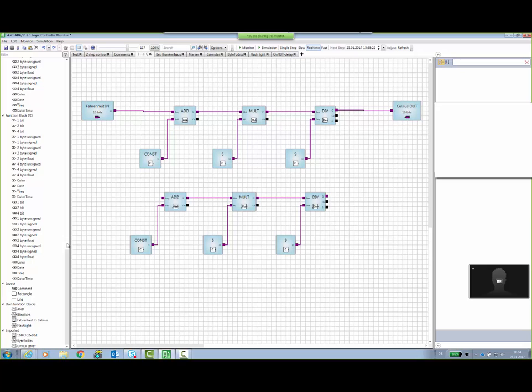To create a function block now, I have to take not the normal KNX inputs and outputs, as we have here, but function block IOs, as you see here on the left as well. So the same data types, but named function block IOs. In this case it's a temperature value, which is a 2-byte float value. So I take the 2-byte float value as a function block input, FB input so-called, and I connect it to this input. And the same I need for the output. I connect it here, that's the output.